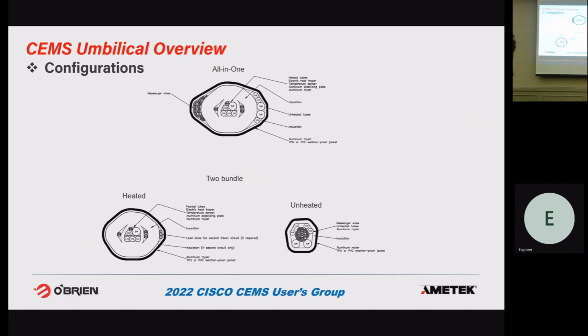So we have a lot of customers that figure on a 400F bundle lasting 5 to 7 years, and then they either replace it or buy one and put it into storage as a spare. As long as you keep the tubing bundle away from external damage like vehicular traffic, and keep it inside away from moisture, it doesn't degrade. We've had customers keep a tubing bundle on the shelf for 5 years and then put it into service as a spare. So that's 5 to 7 years for real high temperature, high current applications.